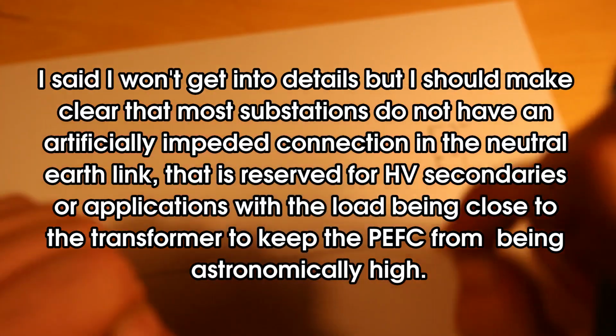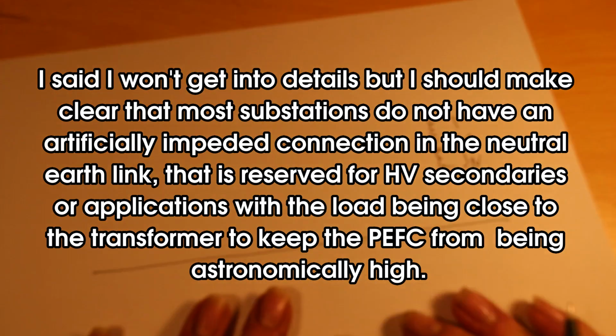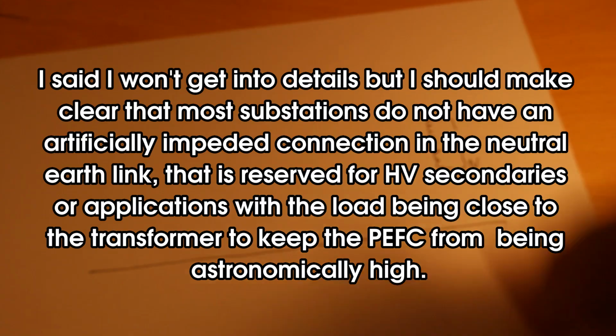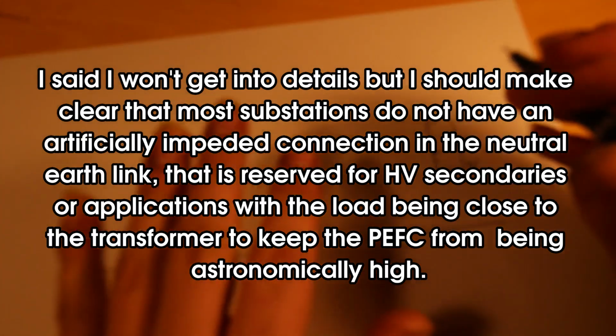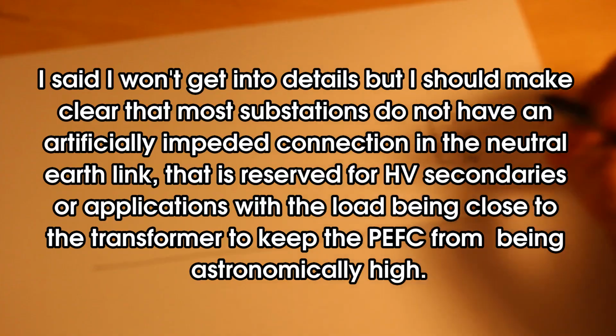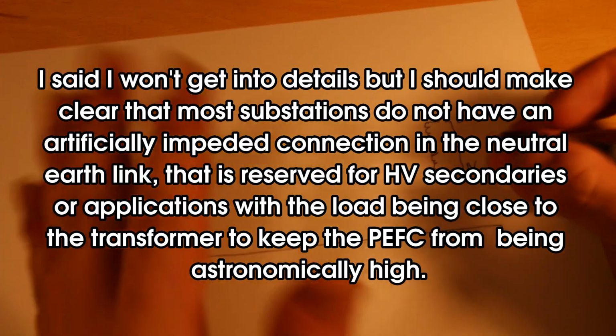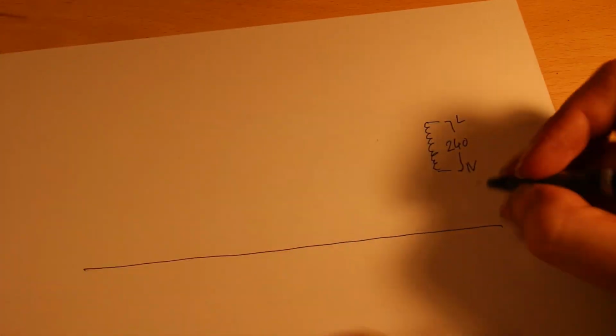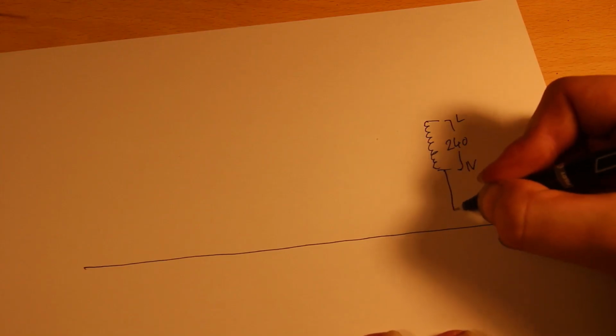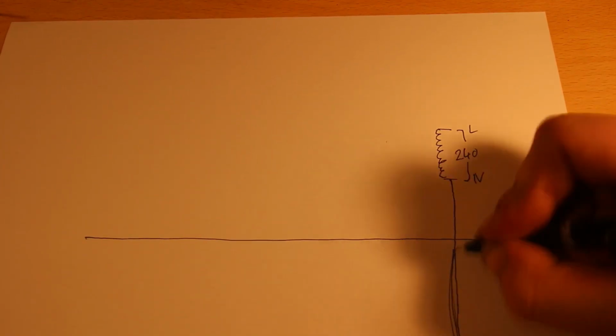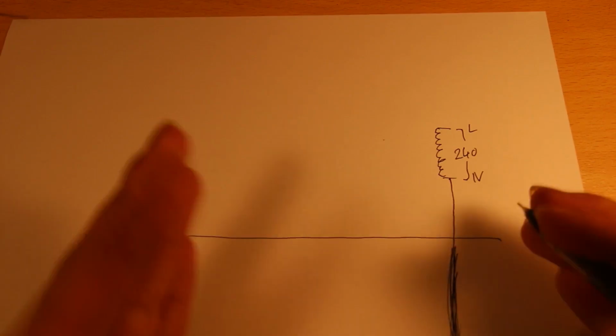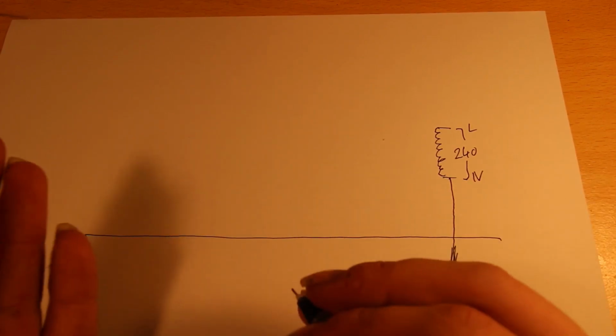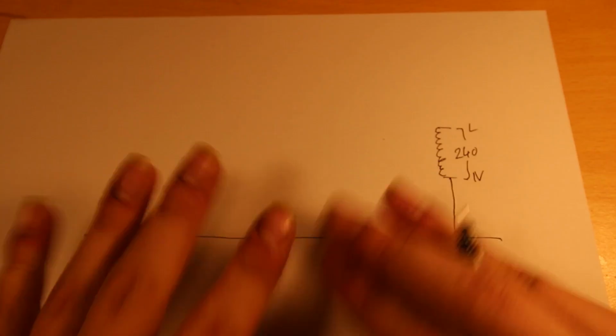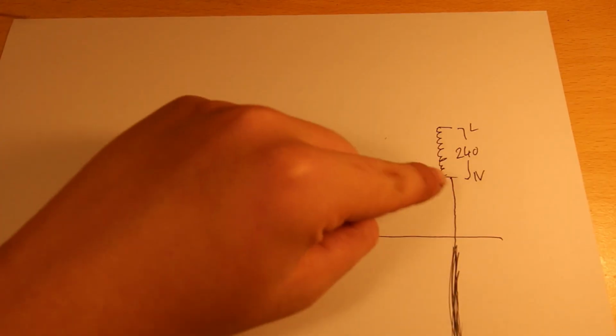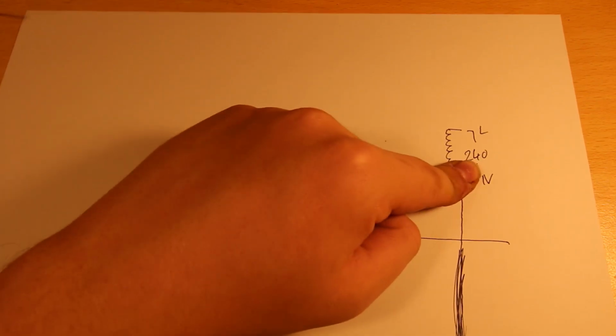I am resisting going into depth about such things because that's what happened last time and it took ages. You have a neutral earthing resistor, but for the sake of simplicity, link. It can be a reactor too. Again, I'm not going to get into that. Link. That goes from the neutral to a lump of metal which is just in the earth. Usually it will be an earth grid for a substation, but again, I'm not going to get into this, keeping it simple. That means that you then connect the neutral to Earth.